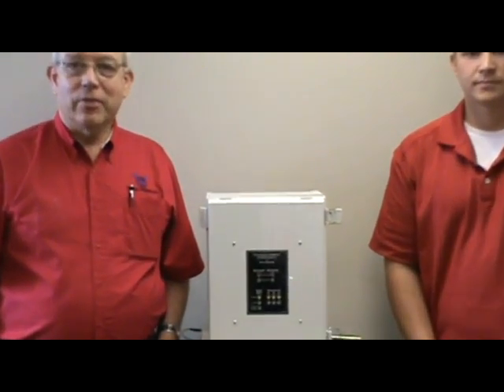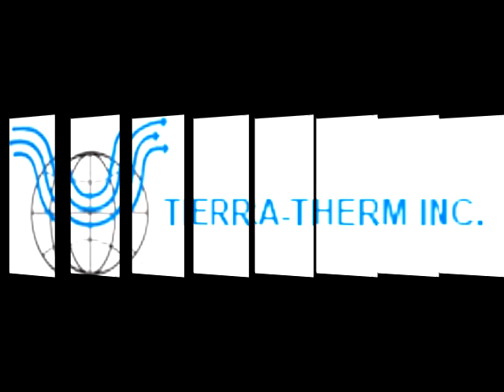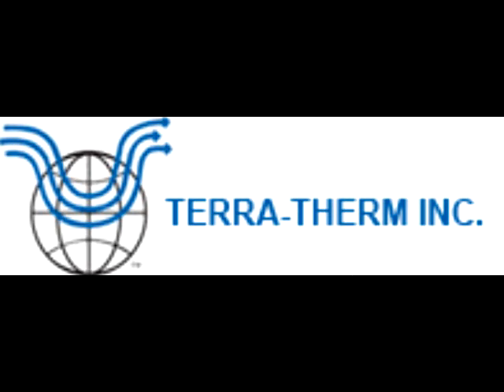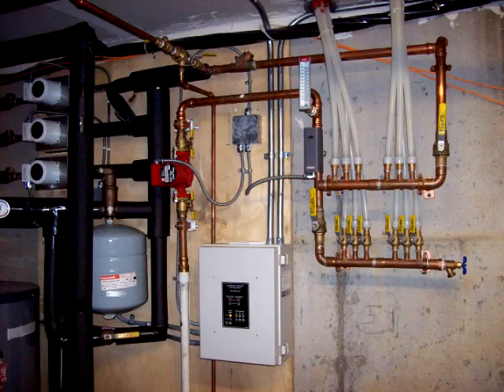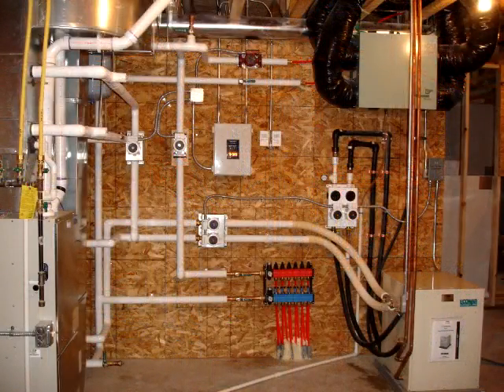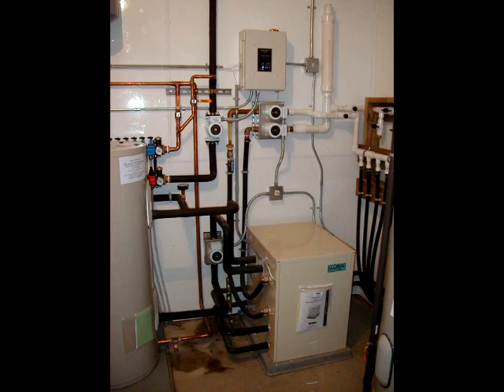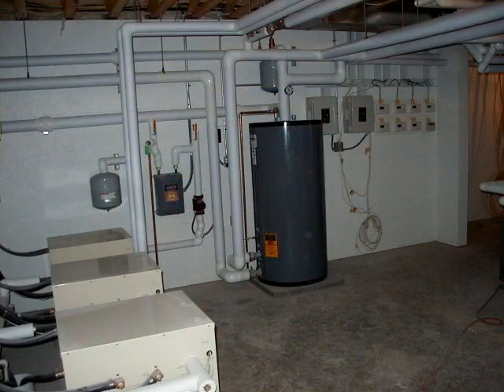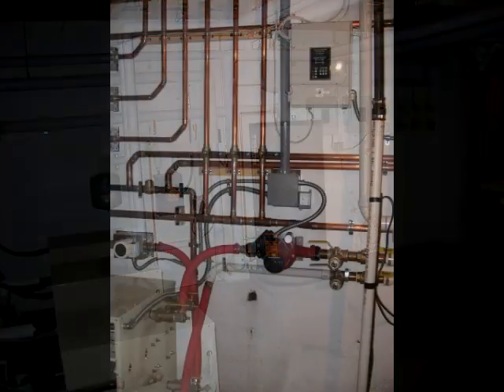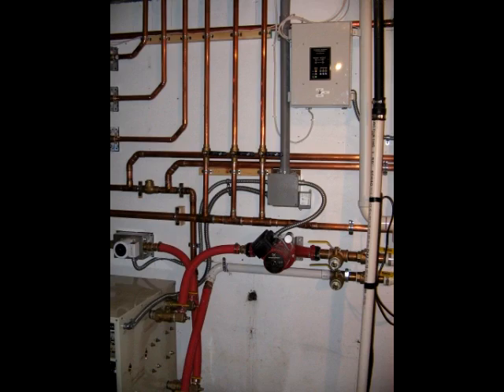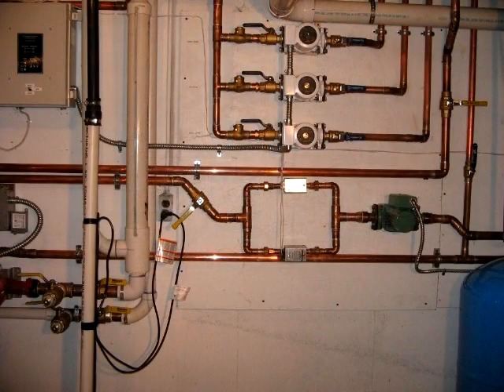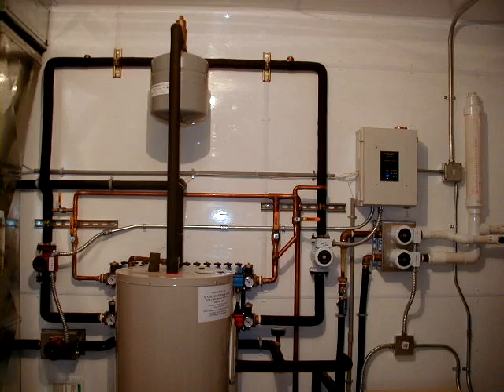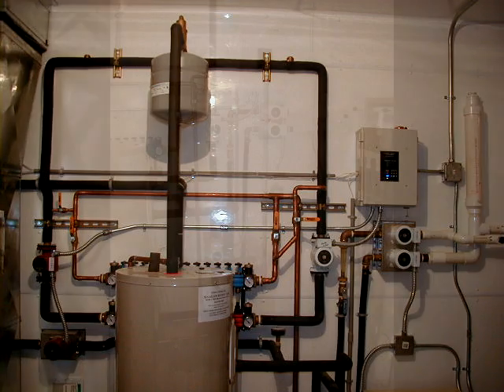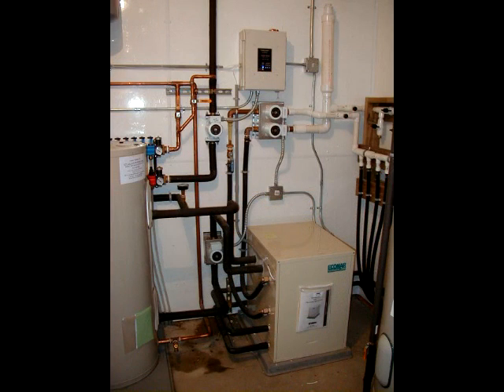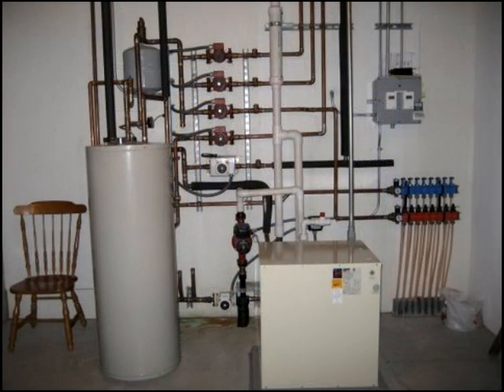Hydronic heating systems have historically been complex systems to design and wire, and were not user-friendly for the homeowner. Terra-Therm's Hydronic Control Module solves these problems with a single place to control all components of a hydronic heating system, and has simple cover-mounted LEDs to allow the end user to know the mode of operation and status of each zone. Terra-Therm's Hydronic Control Module also provides a cost-effective way to provide low voltage control for the entire hydronic system.